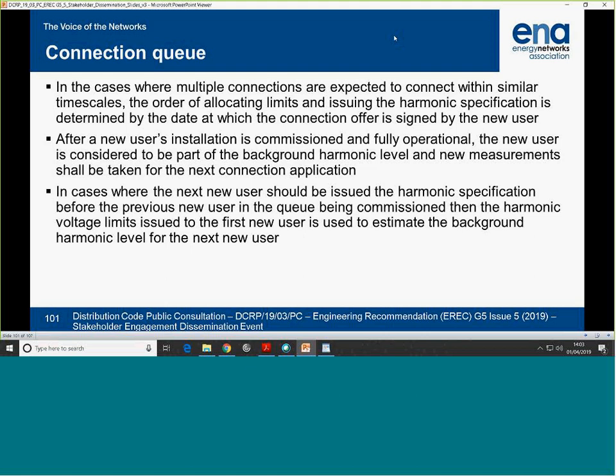As the offer goes out and goes through the process, your information is refined. But at the point when the offer goes out, no harmonic assessment has been done. There's no allocation of anyone's headroom. No process allocation, but you know from the Thevenin equivalent that you've got headroom. Otherwise, you wouldn't be able to do the equivalent. No, we don't. It might be no headroom anywhere, and you just connect. You need to install mitigation. But the harmonic limits and LOPO don't tend to go out with the offer. They tend to go out further on, when we're actually close to connection and we have some information.